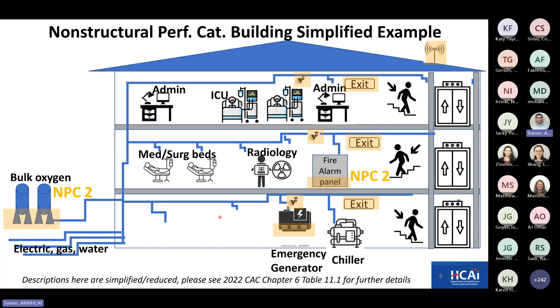So in a state where the building is not evaluated or the building is not braced, it is by default an NPC1 state. In this state, let's say the bulk oxygen is anchored, the emergency generator is anchored, the fire alarm panel is anchored, the exit way, the lighting, those are anchored, and the communication system, and a few more things that get you to NPC2. So again, NPC2 really focuses on the evacuation of a building, not really functioning of a building. Again, as you see, it's a minimal amount of things that we look at for the building for NPC2.